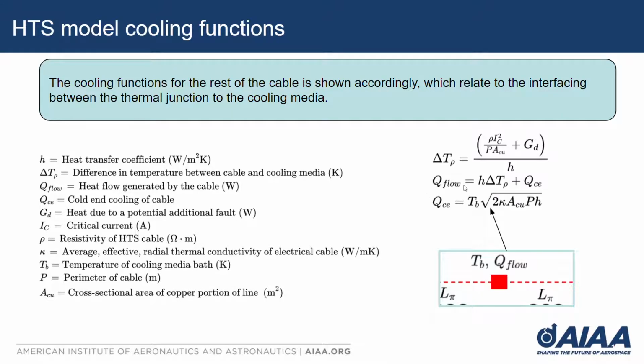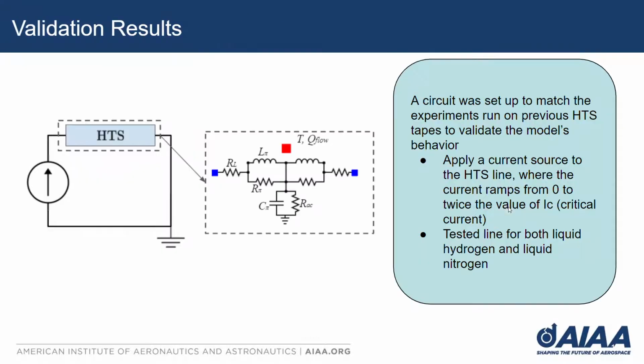The heat flow out of the line is a function of the heat transfer coefficient and temperature difference between line and media, and a cold end cooling function. This cold end cooling function is a function of the cooling bath temperature, the geometry of the line, and the thermal conductivity of the cable.